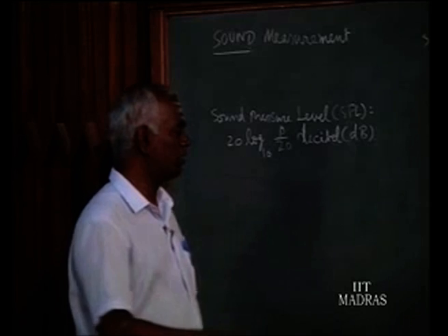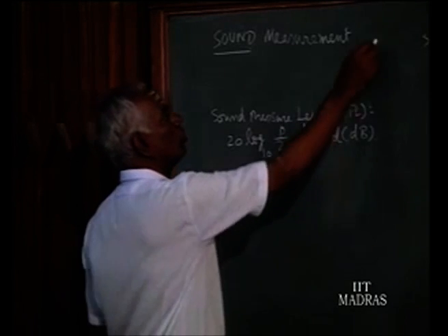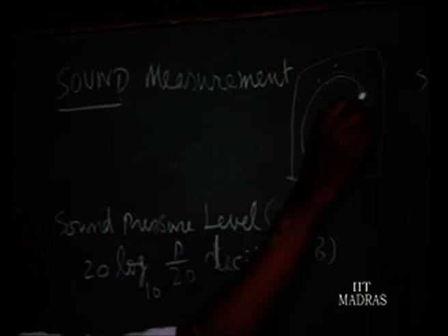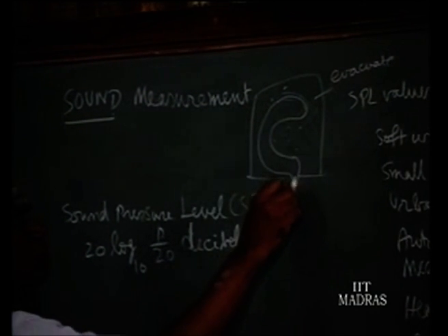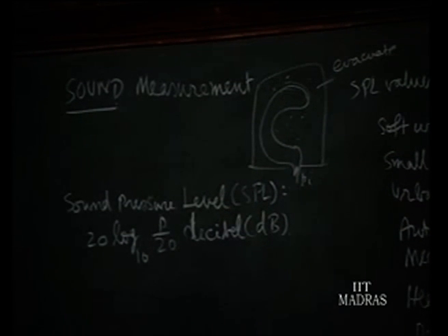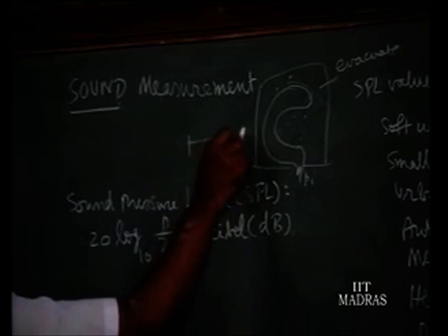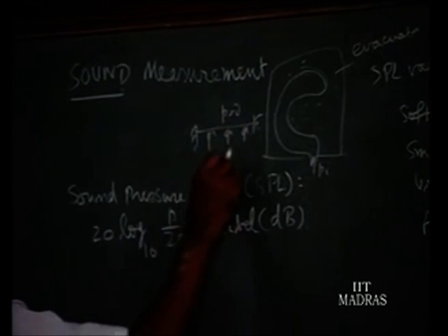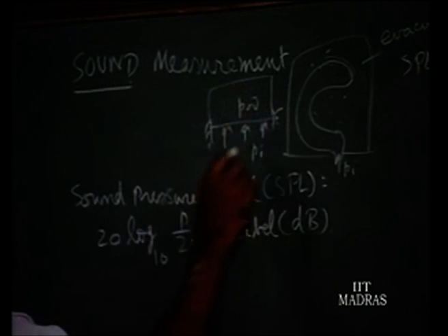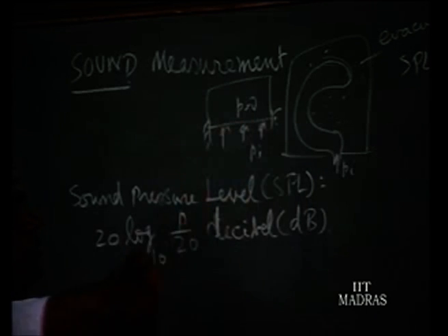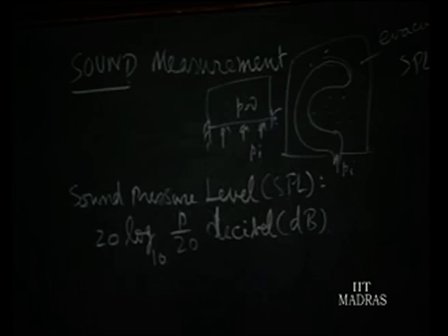If you take a Bourdon tube, which you have seen, and put it in a casing and evacuate the surrounding in which the Bourdon tube is put, then the Bourdon tube itself can measure low pressure or vacuum pressure. Similarly, with a diaphragm, if on this side P is equal to 0 vacuum, and here it is some pressure Pi, then we can measure vacuum pressure lower than atmospheric conditions.